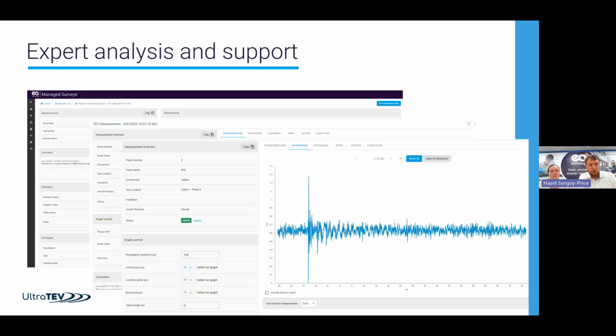The analysis has moved on a long way, so you now see your full detail centrally - your phase plots, your waveforms, etc - and there are things in there to filter out noise and allow you to clean up your plot to look at exactly what is the PD. We choose this on the central data because our device collects all the data up front, so you're not omitting any of the data unintentionally. There are versions out there where these settings are set on capture, but we have the full resolution data centrally, and then we can filter that as required.